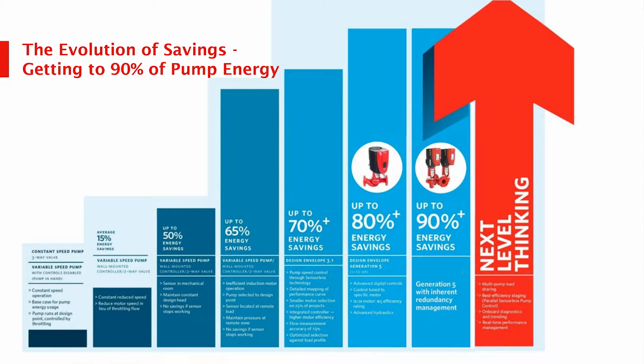Early technology was people adding a drive to a constant speed, constant flow system—they'd figure out they could slow the pump down. Same constant speed pump, just running a bit slower, with less throttling. That was a good first start, but that's early 90s technology.